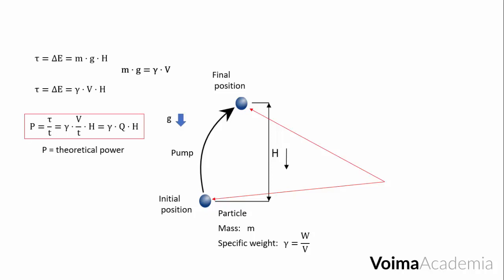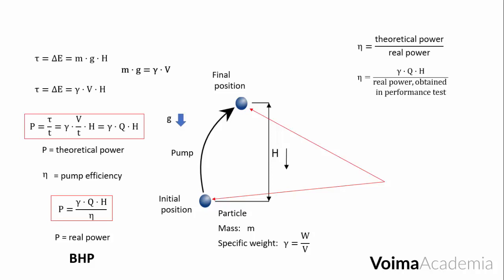Of course, the power that we'll find using this expression will be the theoretical power. To find the real power, we must know the efficiency of the machine that will perform the work. It is a number smaller than one. Note that it divides the theoretical power. So, the real power will be greater than the theoretical power. This will be the power that we must supply to the axis of the pump. It is known as the brake horsepower, or in short, the BHP.